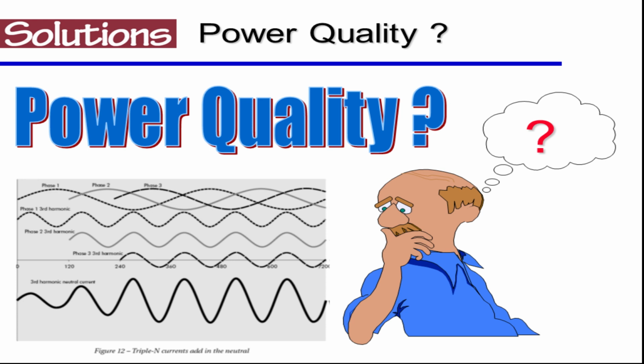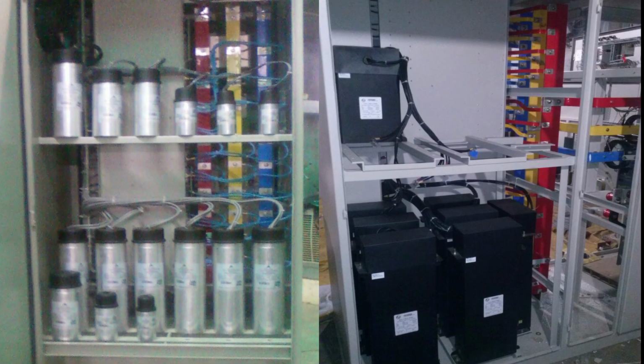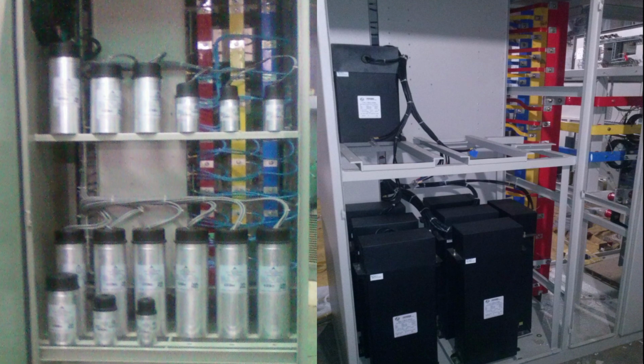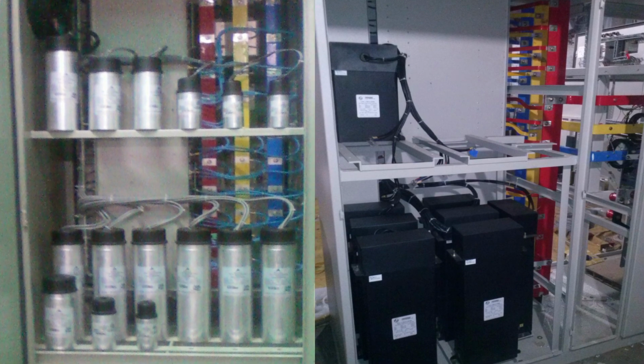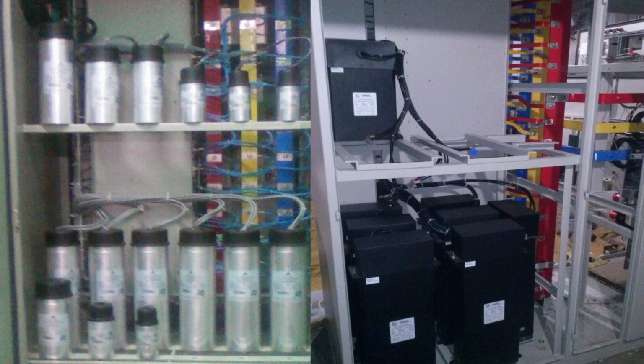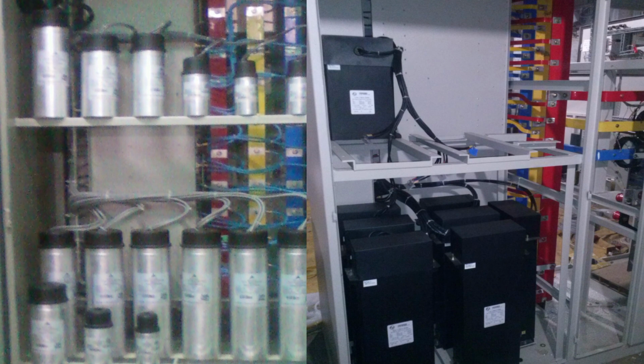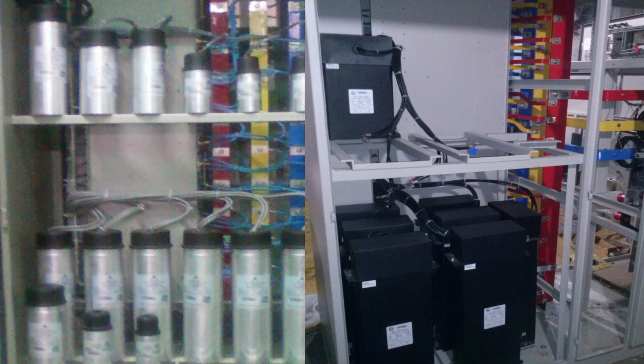In this video, we will go through 5 basic questions and its answers to get better understanding of power quality and harmonics related issues. Do you think harmonic distortion is caused by turning on power factor correction capacitors? Power factor correction capacitors do not cause harmonic distortion, but can worsen harmonic conditions due to resonance.